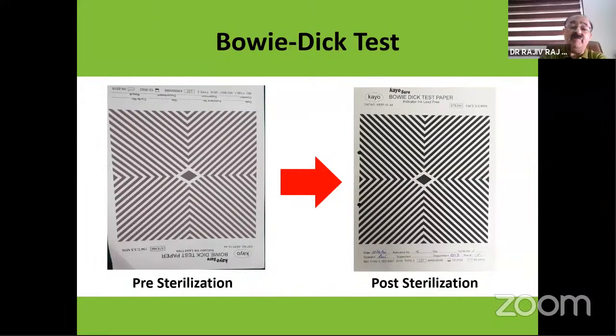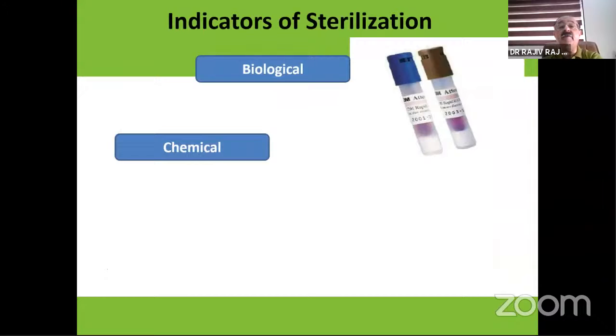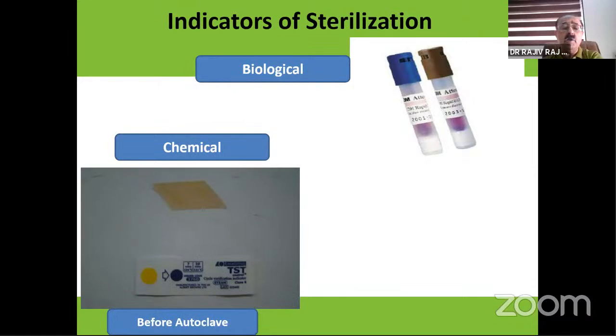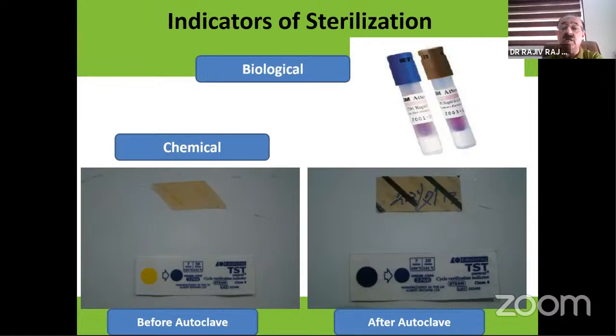Now, at the time of autoclaving, before the first cycle, a pre-sterilization and a post-sterilization Bowie-Dick test is conducted to make sure that the autoclave is working well. A leak test is also done. There are various indicators of sterilization, biological and chemical. Now, the chemical indicator, as you will see, there are 2 shown here, one below and one above, and the color changes from yellow on the left-hand side to dark blue on the other side out of the autoclave. Similarly, biological indicators are also used.